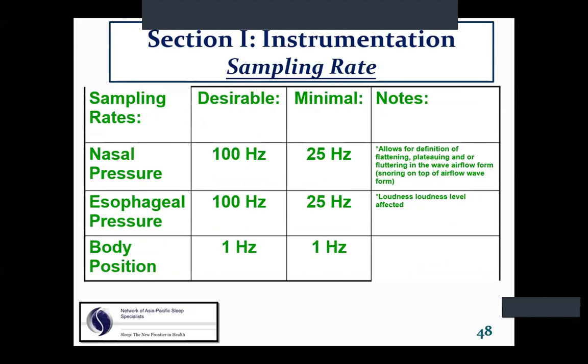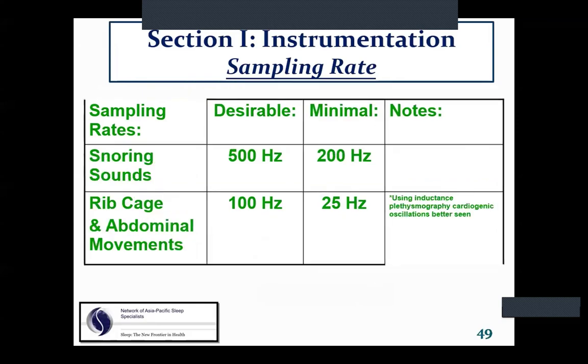Again, you have to make sure that your sampling rate in each channel is set appropriately. Now, it's not uncommon when I'm in the field to have technologists who are aware of low filter, high filter, and notch filter. I don't find many that know even where to change the sampling rate. That's because most labs don't even train that, because they don't want it to get changed and mess up the recording, because it can grossly corrupt your data, not only making it look funny, but make it unreadable. So be aware of your sampling rate, desirable and minimal. And I listed it for every single channel that we record.